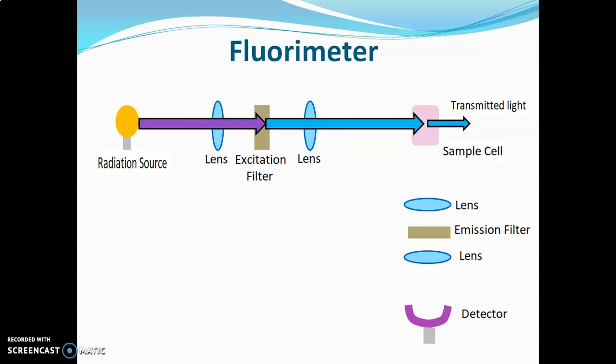Due to absorption of UV radiations, the sample gets excited and starts fluorescing. The fluorescence light passes towards the emission filter, which absorbs UV radiation and only visible radiations are allowed to pass towards the detector. Visible radiations hit the surface of the detector, which measures the intensity of light.